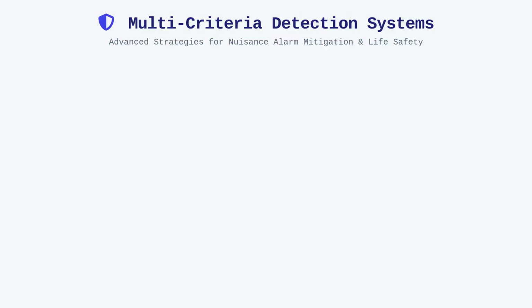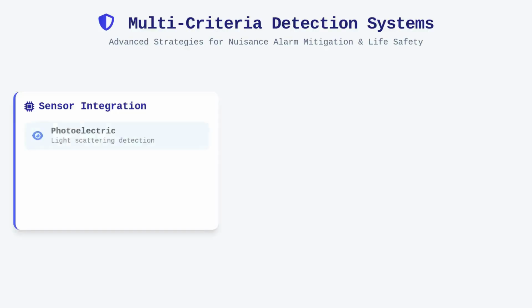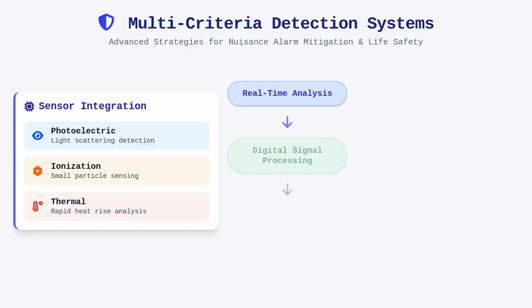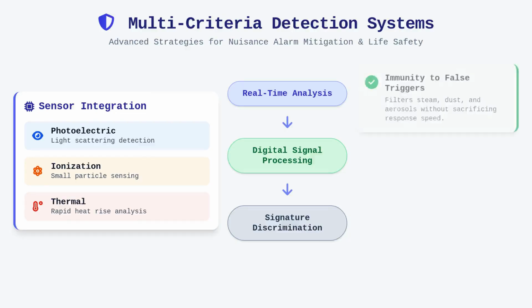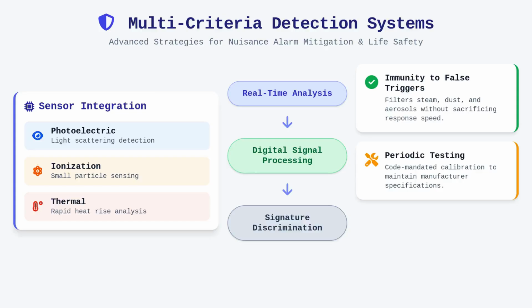Modern systems frequently employ multi-criteria detection algorithms to handle the persistent challenge of nuisance alarms. By integrating inputs from photoelectric, ionization, and thermal sensors, these systems can analyze the signature of the air in real time to distinguish between hazardous smoke and common contaminants like steam, dust, or cooking aerosols. These digital signal processing techniques allow for a much higher immunity to false triggers without sacrificing the speed of response during an actual fire. However, the integrity of these systems relies entirely on periodic testing protocols mandated by code to ensure that sensitivity calibration remains within manufacturer specifications.